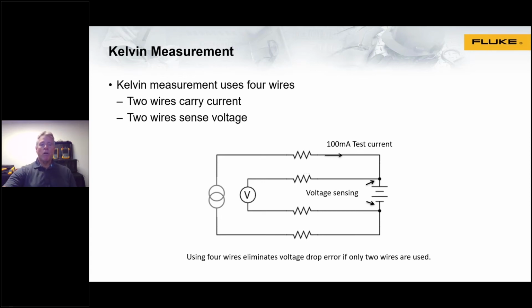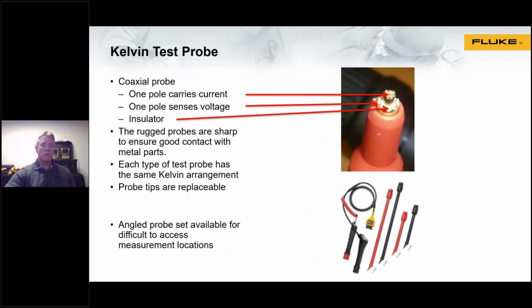So essentially, a 4-wire measurement allows you to compensate for the test lead resistance and take that out of the equation, along with the voltage drop that would occur because of your test lead resistance. That's why a 4-wire measurement is required for battery internal resistance. This is a look at one of the actual probes, where one of the probes carries current and the other one senses voltage. Again, we're making a 4-wire measurement. There would also be a black or negative probe, which would have the same construction.